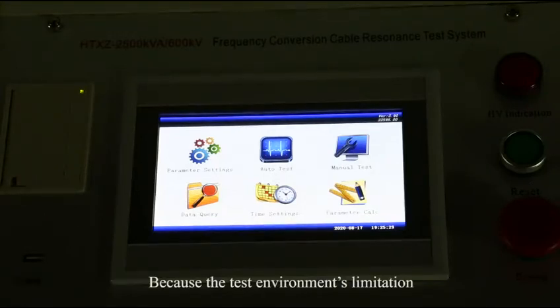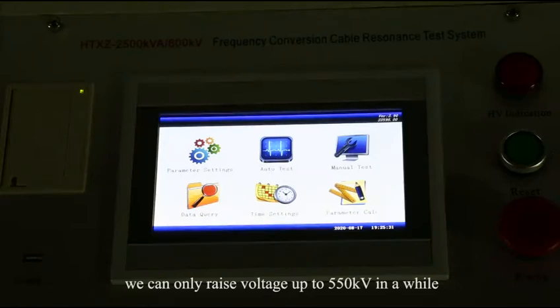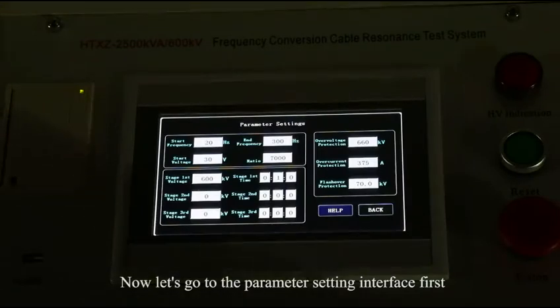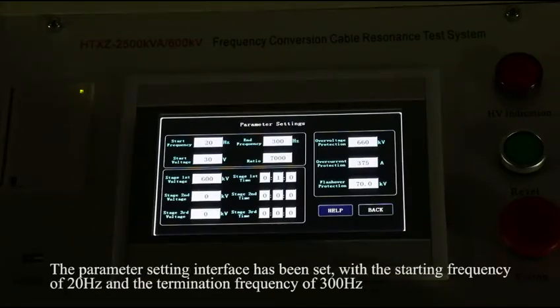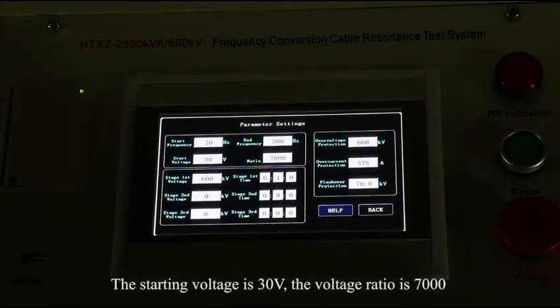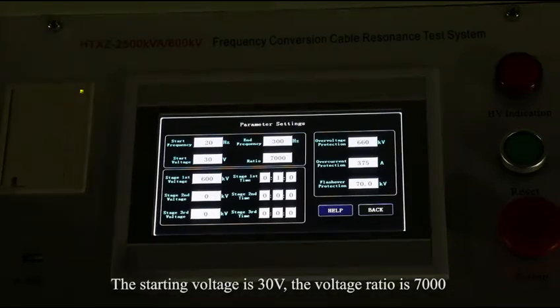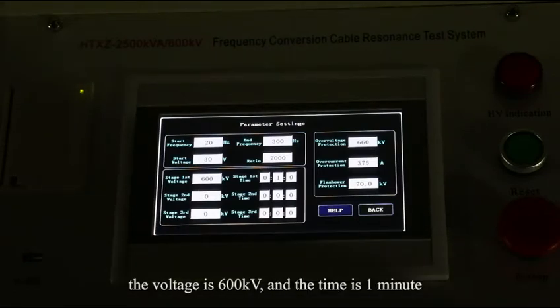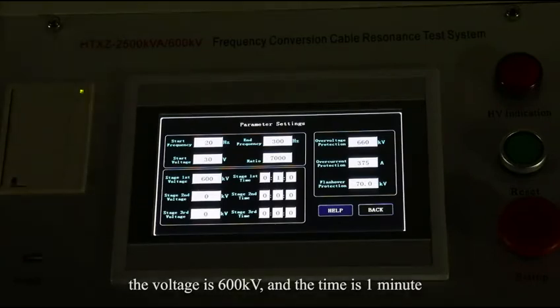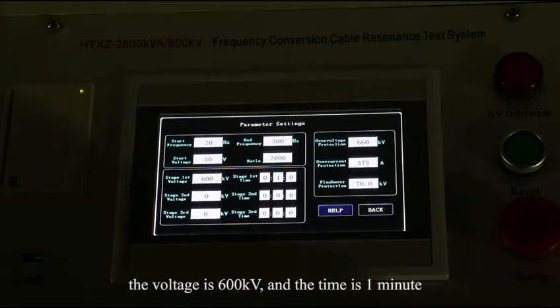But because of the test environment's limitation, we can only raise voltage up to 550 kV in a while. Now, let's go to the parameter setting interface first. The parameter setting interface has been set with the starting frequency of 20 Hz and the termination frequency of 300 Hz. The starting voltage is 30 volts. The voltage ratio is 7000. The voltage is 600 kV, and the time is 1 minute.